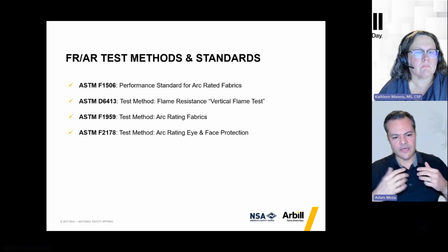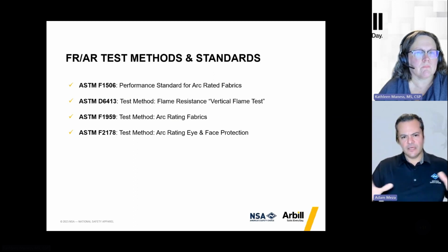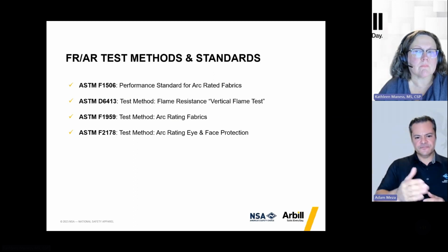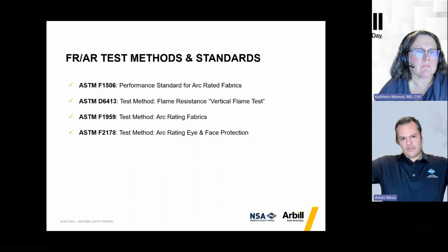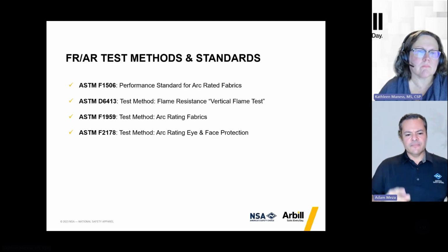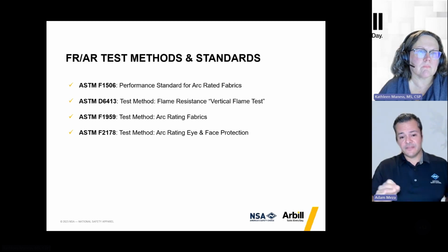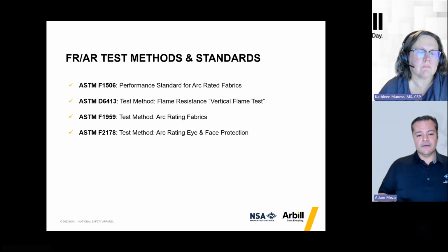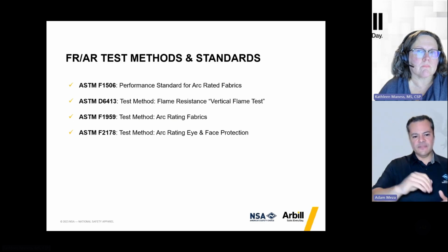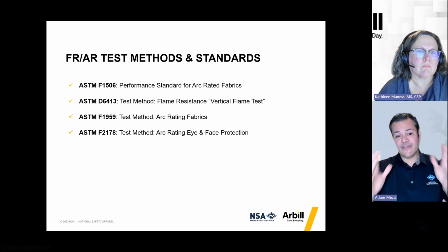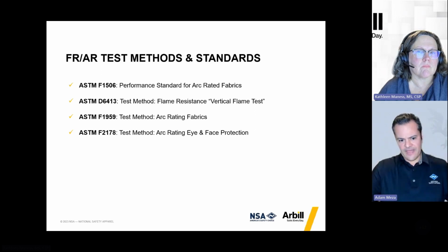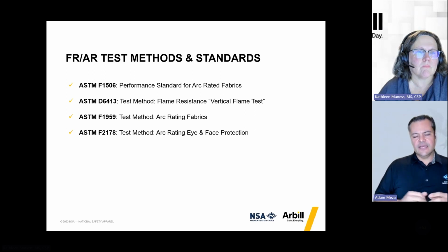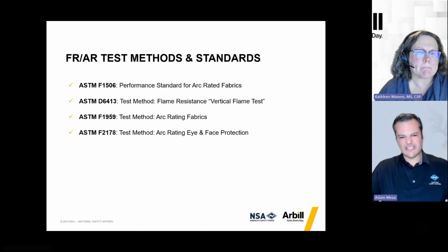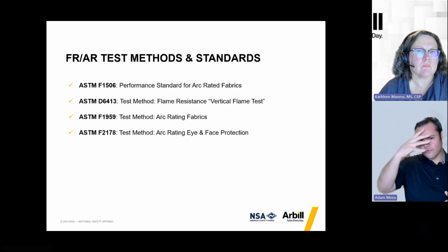Now, here are some of the test methods and standards associated with electrical safety. 1506 is a performance standard, an overall kind of arcing umbrella standard. 6413 is a test method, a vertical flame test, not a standard. Then you have the 1959 test method for a fabric, for arc rating of the fabric. And 2178 is the arc rating test, basically a 1959 test method for a hood, and you'll also use that for a portion of a hood, like a face shield.